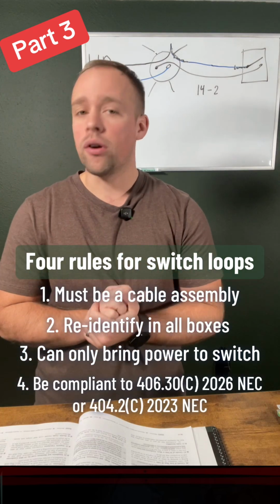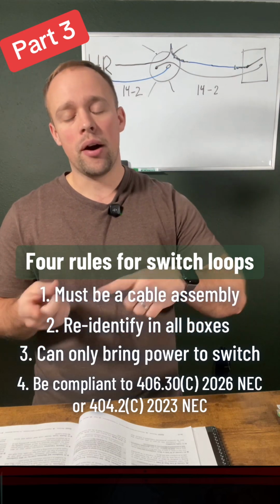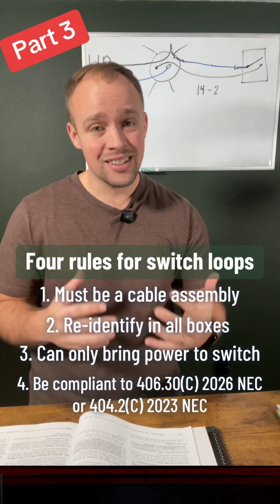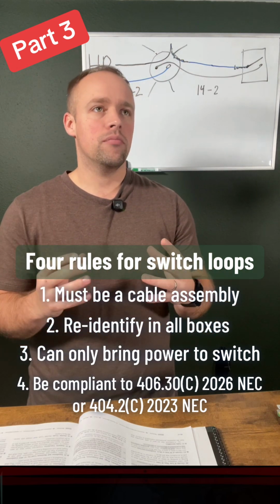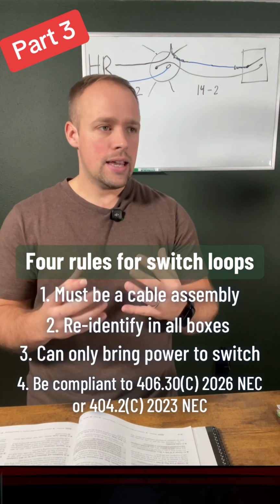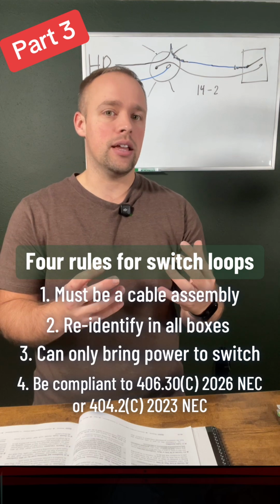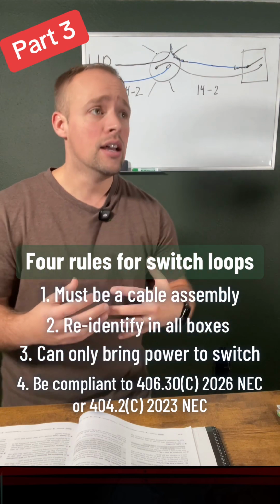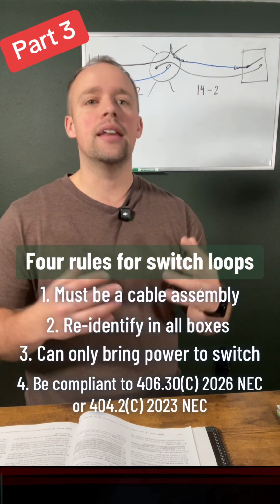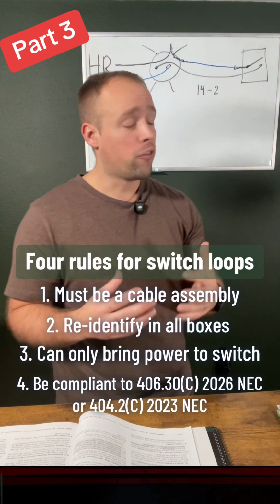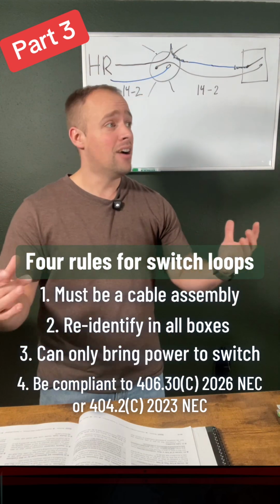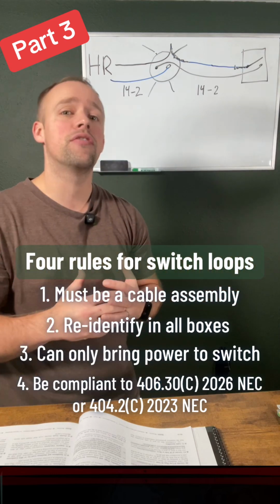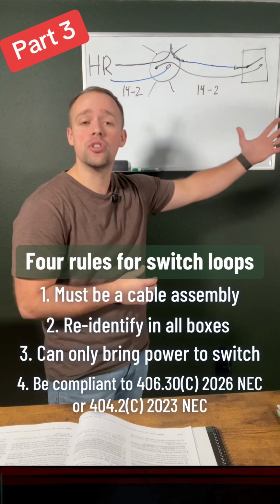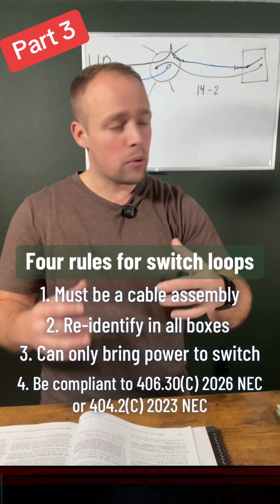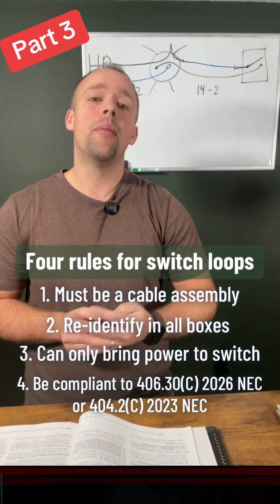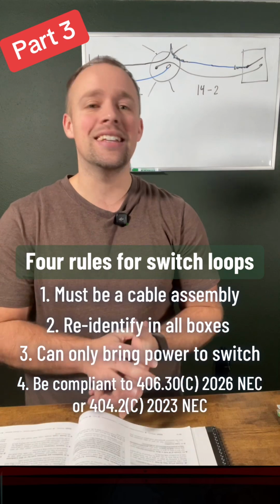The 4th rule that I want to bring up is a rule that I talked about in a previous part when we talked about Article 406, where it told us that you need to have a neutral in a switch box in habitable rooms and occupiable spaces. You need to have at least 1 neutral in a switch box in a room, basically. Okay, so before you do a switch loop, you need to look at your room and say, okay, are there multiple switches controlling the same light? Because if there's not, then you probably can't do a switch loop like this, and you need to have at least 1 neutral present in a switch box in a room. So those are my 4 rules for switch loops based on the NEC code standards.